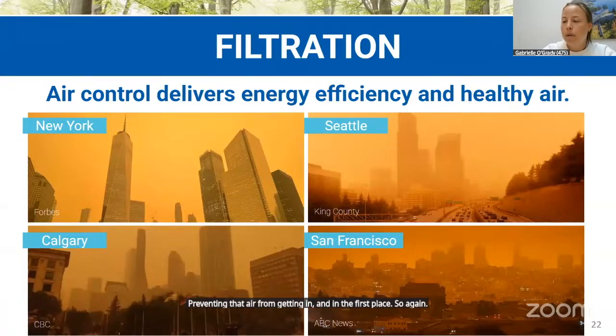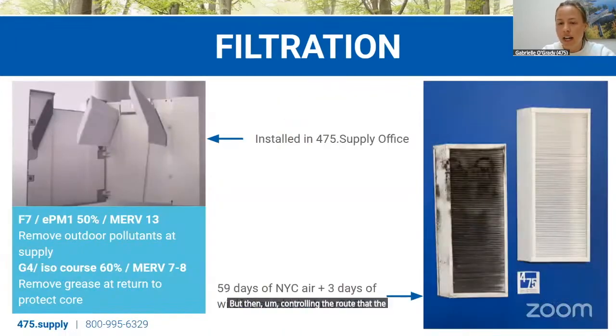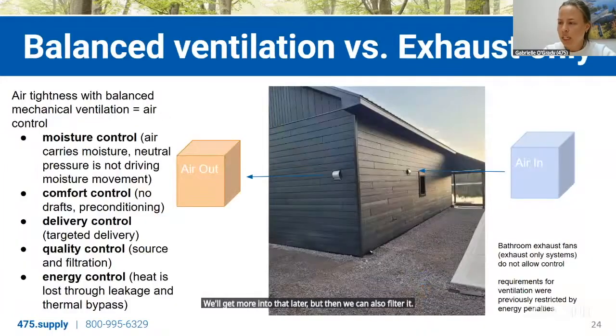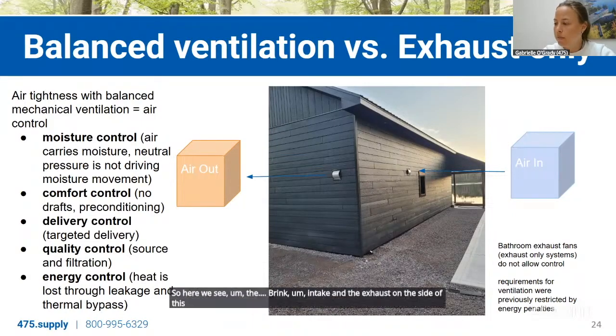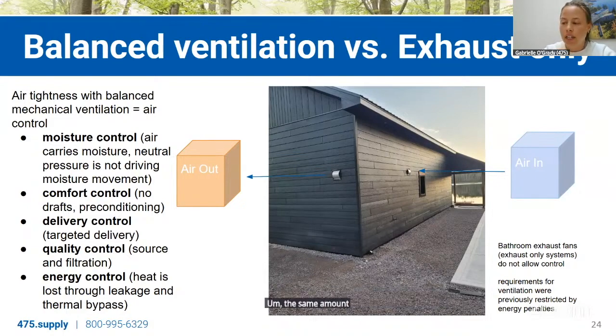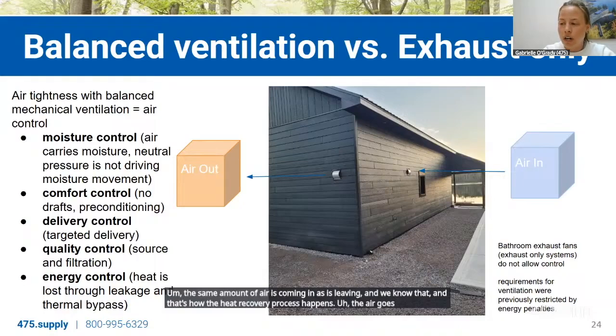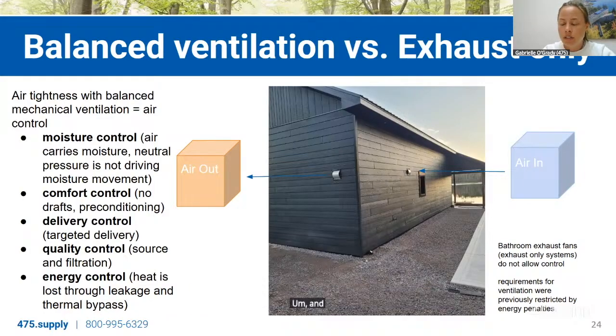So again, airtightness, but then controlling the route that the air gets in and filtering that. So that's what a mechanical balanced system can do. We know exactly where the air is coming from, and we can place that supply location very intentionally where the freshest air possible is located. We'll get more into that later, but then we can also filter it. So here we see the Brink intake and the exhaust on the side of this home, this beautiful project here. The same amount of air is coming in as is leaving, and we know that. That's how the heat recovery process happens. The air goes through the core and the air streams pass each other. And that leads to neutral pressure in the home.